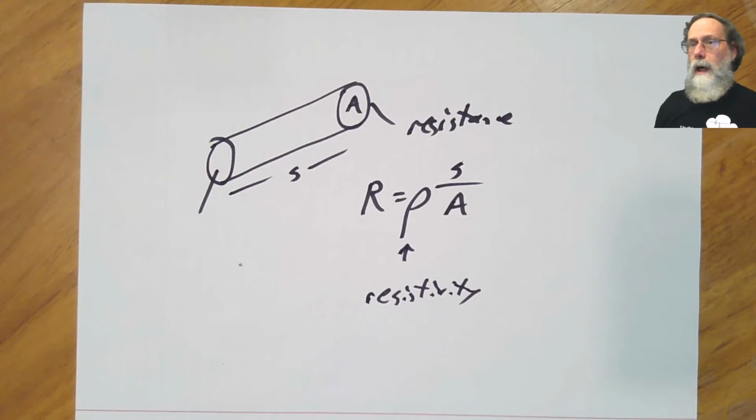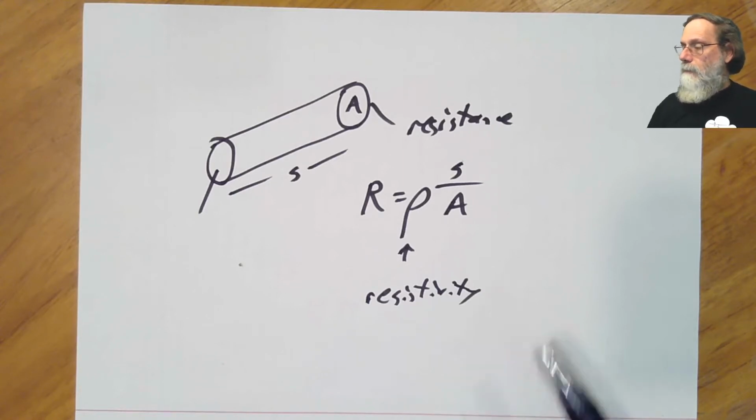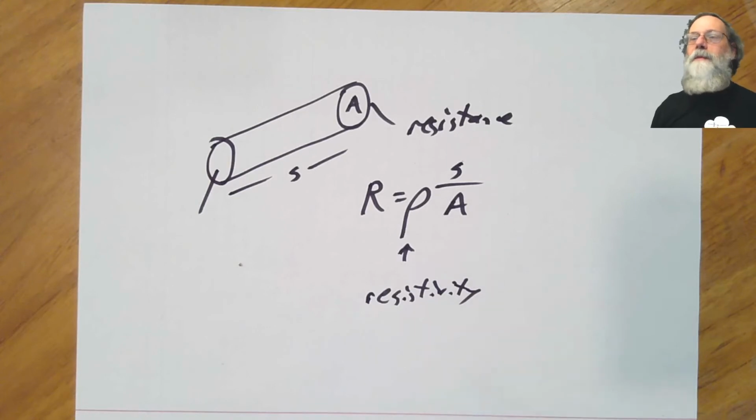So what we usually have is a different geometry for the electrodes, but fixed. We fix the geometry, make the electrodes rigid, put them in the solution, and then measure the resistance between the pair of electrodes. We have to correct then for the geometry of the arrangement of the electrodes that we have.